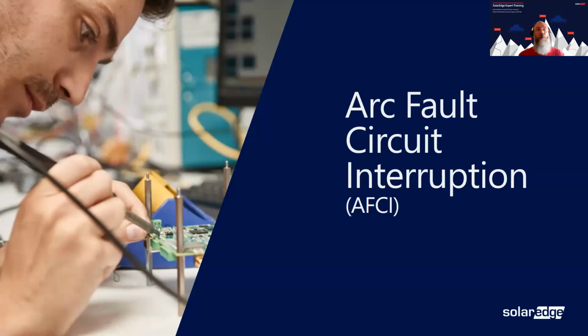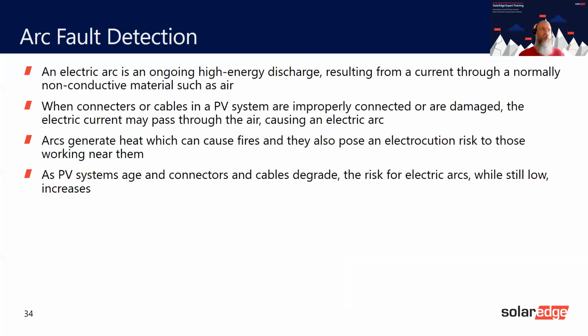So now we're on to the arc fault circuit interruption. I did touch on this before. There's only a couple of slides, but basically all our inverters going back to 2016 have this ability, and that's to do with the communication board. So you can update an older version, put a new communication board on, and it will do the same thing. Basically, it detects an arc, and once it detects an arc, no matter how big or how small, it will then turn the inverter off.